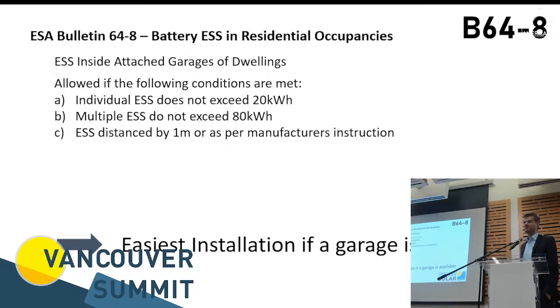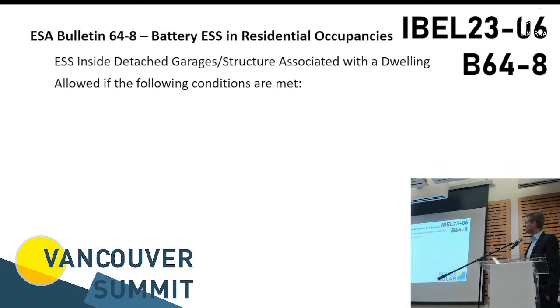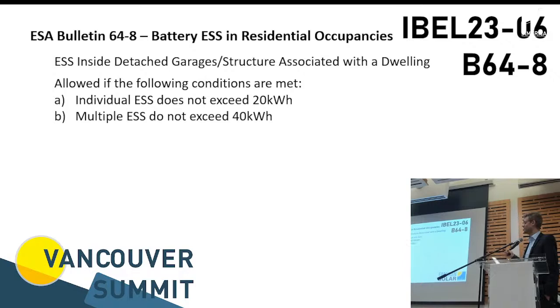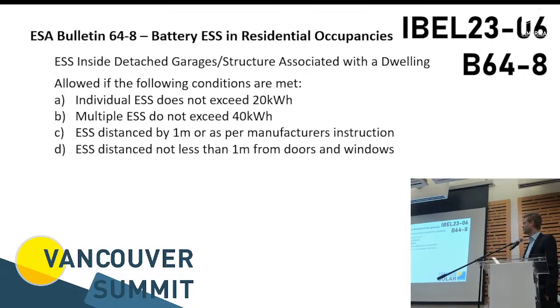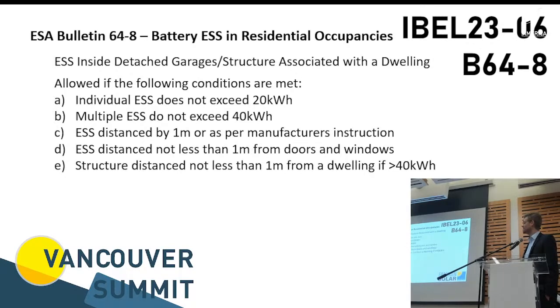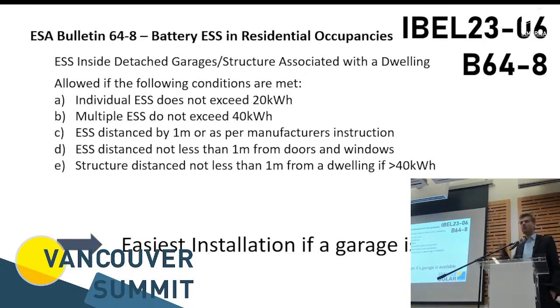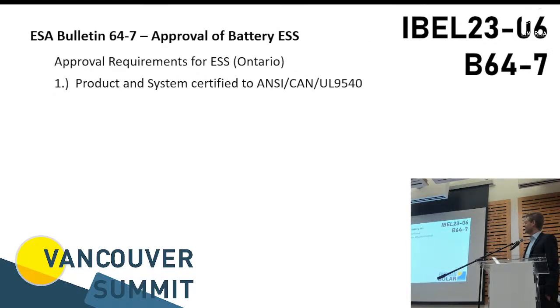And sometimes that's available, sometimes it's not. If a customer has a townhouse and there is no garage and no real space, then of course it gets more and more difficult to place those systems. And then we have another option, and that's the best if it's available. For example, it's a farm and they have a little garage that's completely detached. Then you can pretty much do whatever you like. You can do the 20 kilowatt hours in one system, the same requirements, 40 kilowatt hours for multiple systems, the same spacing requirements, and you can actually exceed the 40 kilowatt hours and go all the way up to 80 kilowatt hours as the maximum capacity of that system. Again, if you have that, that's the best spot to install it.